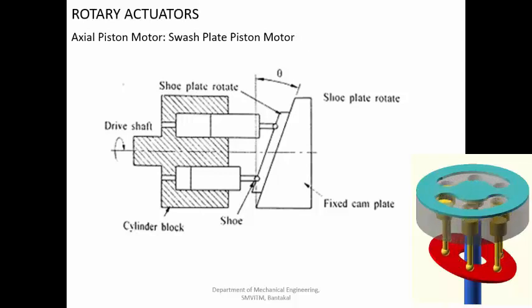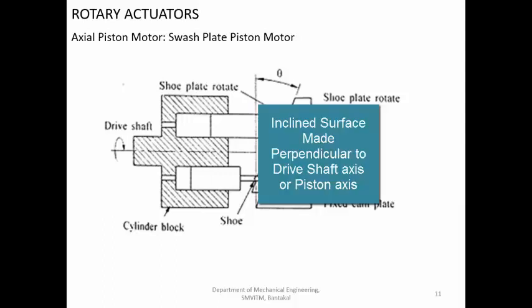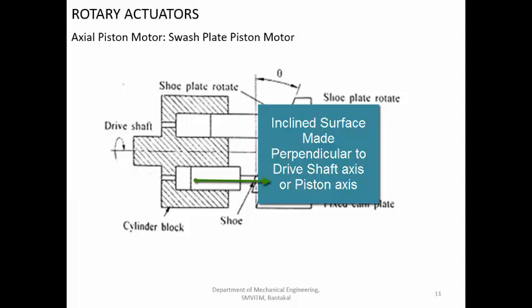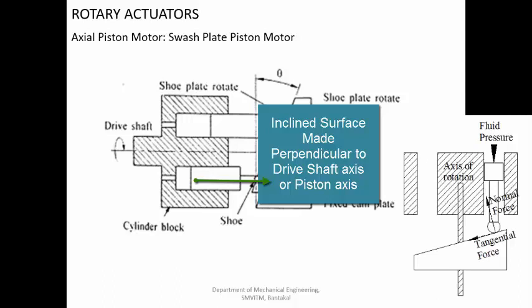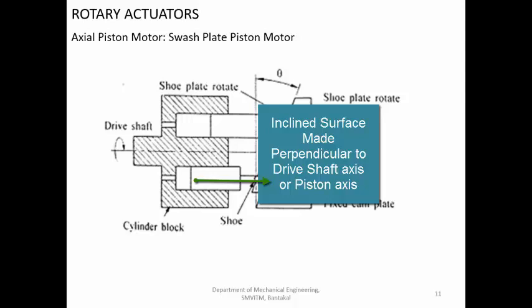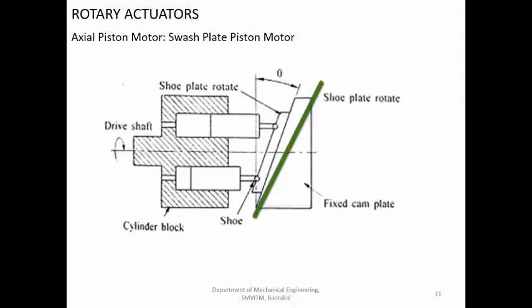Now what happens if this inclined surface is perpendicular to the axis? If the inclined surface is perpendicular to the axis and you supply high pressure fluid, the piston will come outward and try to push the flat surface backwards. There will not be any motion generated because there is no tangential component — no component of force along the surface of the plate. There is only force perpendicular to the surface, so no rotary motion is possible. If the angle is more, the stroke length of the piston will also be more.